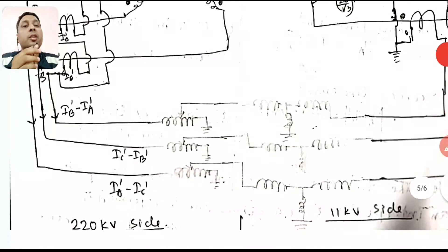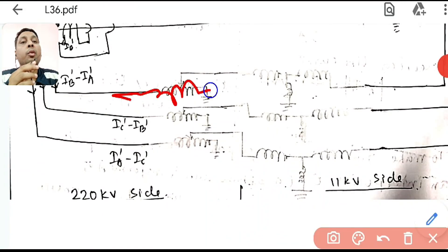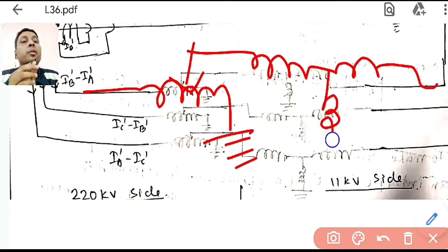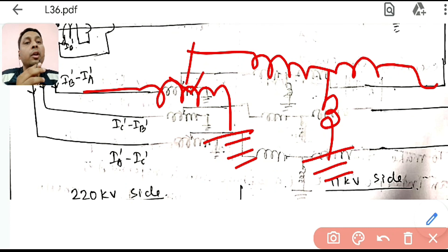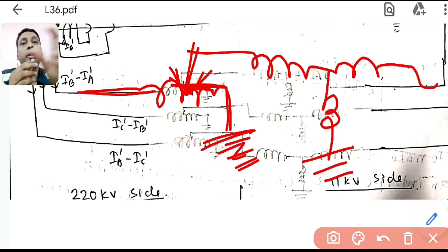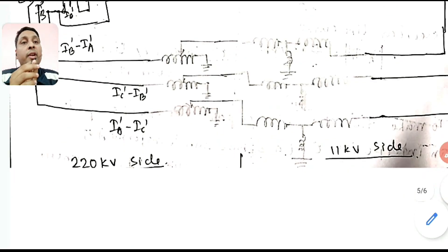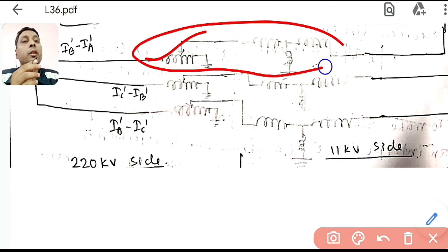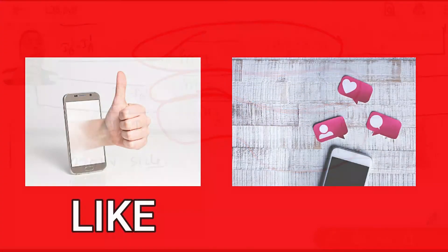In the connection diagram, the auto-transformer (interposing CT) is placed in the pilot wire on the 220 kV side. One terminal is grounded and the output is tapped at the appropriate point to give the required ratio. This is shown for one phase; all three phases are connected similarly to the restraining and operating coils of the percentage bias differential relay. This concludes the numerical portion of differential protection for a three-phase transformer.